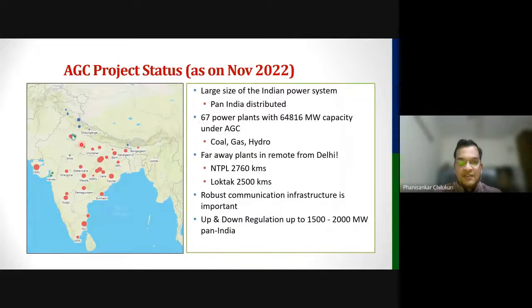So we have so many coal, gas and hydro plants under AGC. From Delhi, all these plants are controlled from the National Dispatch Center. From here, we control NTPL, which is around 2,760 kilometers far away. We control Loktak power plant in the northeastern region, which is around 2,500 kilometers far away. So you understand that robust communication infrastructure is important for AGC. Already there are fiber optic cables laid from Delhi to NTPL, Delhi to Loktak. That is why we are able to control these power plants. And this AGC at present does 1,500 to 2,000 megawatt of generation up and down pan India continuously.